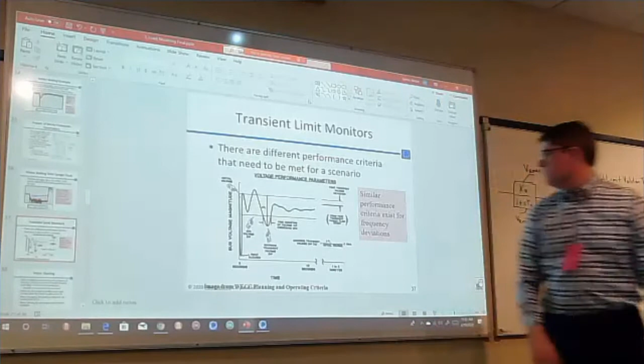What this is showing you is the voltage magnitude as it progresses over time. Something happens and the fault happens, then the fault clears. We don't really care what the voltage is during the fault, because clearly it's bad. So your criteria is telling you what happens after the protection system happens - what are the rules for how I have to recover?